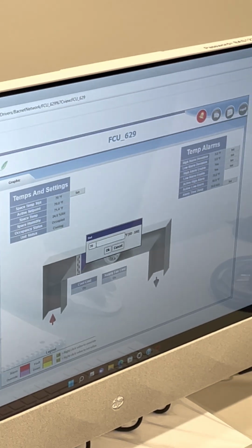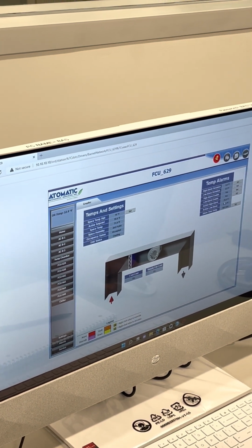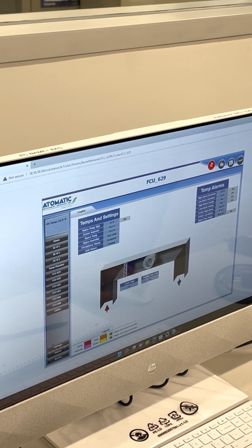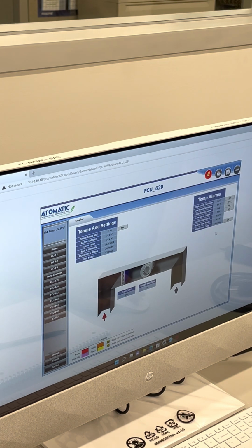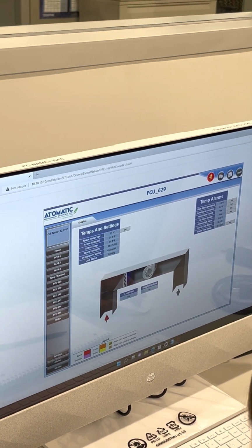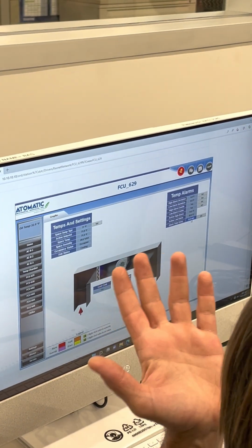So you know it's 75. If we went back to 71 here, once it sees the active, you should see that bump up to 76 and 65 or whatever like that. So it follows suit whatever the active set point is at that time. There you go, there's 76 now and 66. Time delay, it's all in minutes. I got it at 30 minutes right now. We'll have to see how it goes.